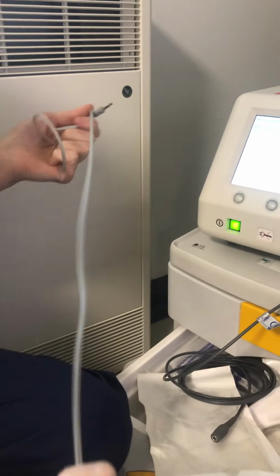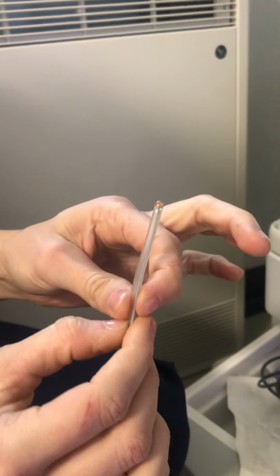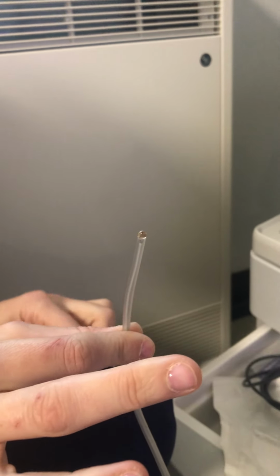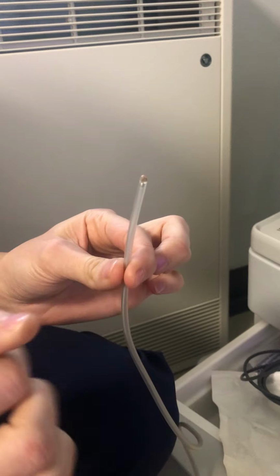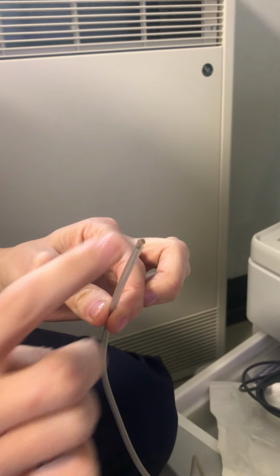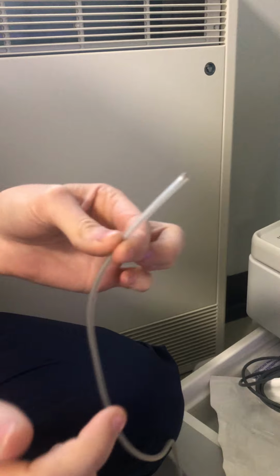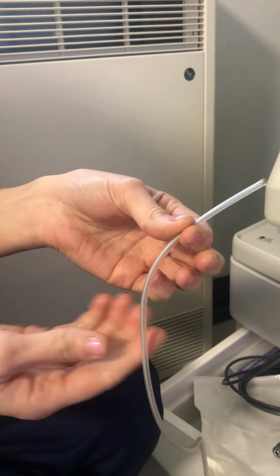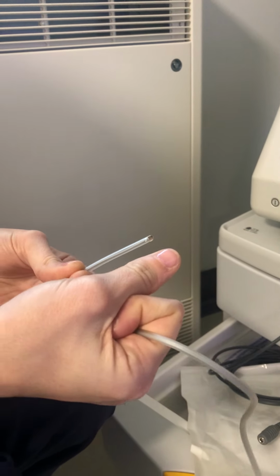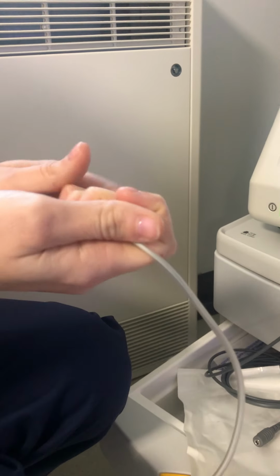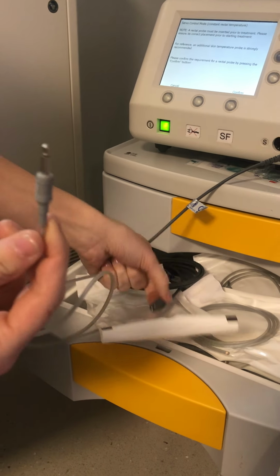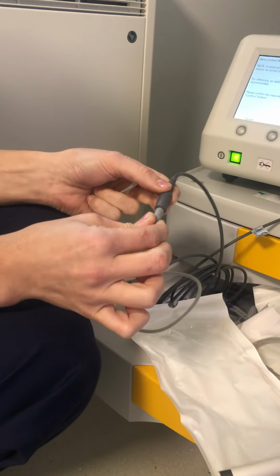So all you need to do is get your rectal probe, and as we all know, it says it in our blue cooling file in the room, you need to measure 6 centimeters and pop a little steri strip wrap around the bottom and then put a mark with a pen, so you know you're only going to insert that 6 centimeters. Then you put a little bit of the lube on it, pop it in, and a Tegaderm to attach that to the leg. Once that's in the baby and you're happy that's in the baby, you take the other end, the aux lead end, and attach that into the cable, like so.